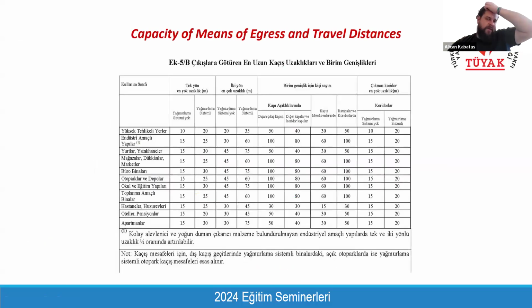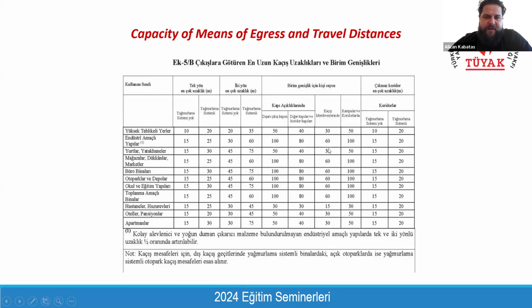As you can see, if you have a sprinkler system, the limitations become smoother and more flexible, and it changes your design restraints. Even if you don't need a sprinkler system as per the Turkish fire code, according to your design requirements and the architectural design of your building, you can prefer to ask the mechanical designer to provide a sprinkler system.